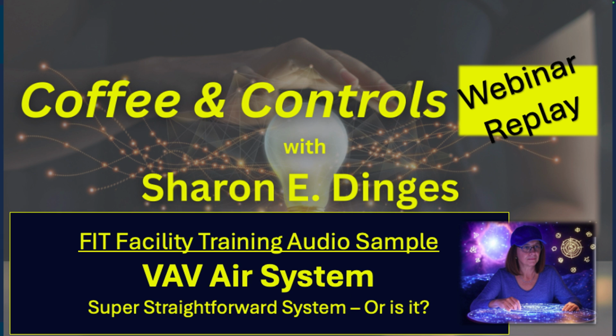So what's going to happen is that damper, that air valve, is going to back off a little bit. And there are different styles of it. Some of them pay attention to how much air is moving through them. Others just by proxy estimate, right? Because they've done testing for their device, for their VAV, variable air volume box. They've got a curve associated with that damper position. Others actually have what's known as an airflow measurement ring on the outlet. So you can actually say this many CFM, or cubic feet per minute, the measure of air volume being delivered.